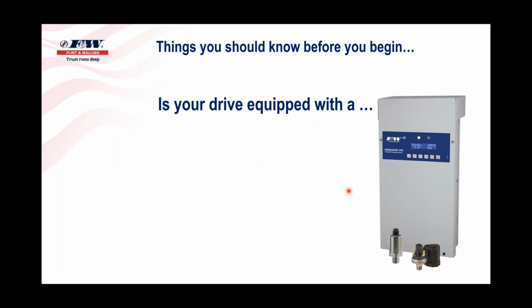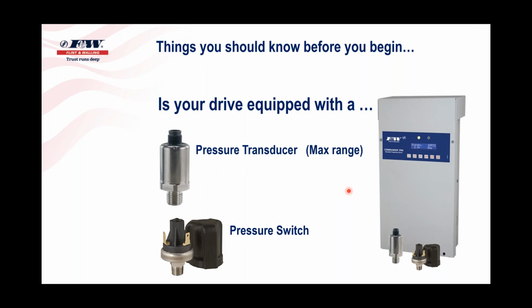So a couple things about the drive too, before we go into the programming: is your drive equipped with a transducer or a pressure switch? Now, talk about this for just a second too. Back in 2014, when we launched this drive, we launched it at the NGWA show. I think it probably was in Vegas at the time, or Nashville, I can't remember. But when we went to the show, we were showing this F&W drive here, and we had brought a lot of contractors in for input. Okay, so you all have been selling various brands of drives out there. If you were part of the design team, what would you like to see improved upon?